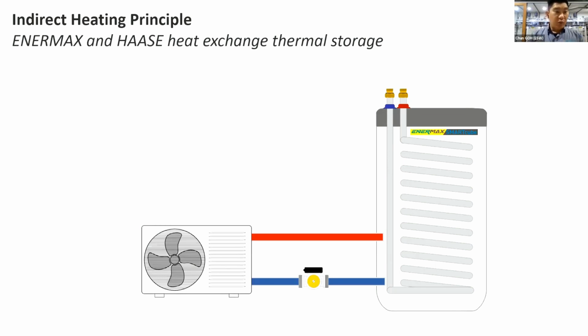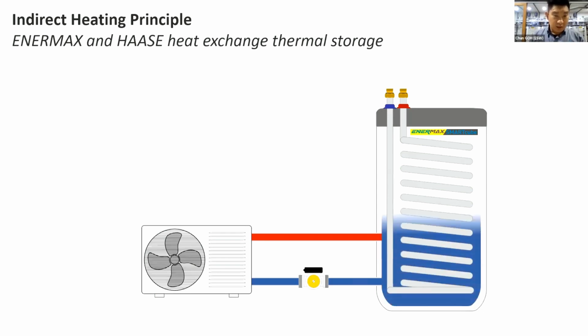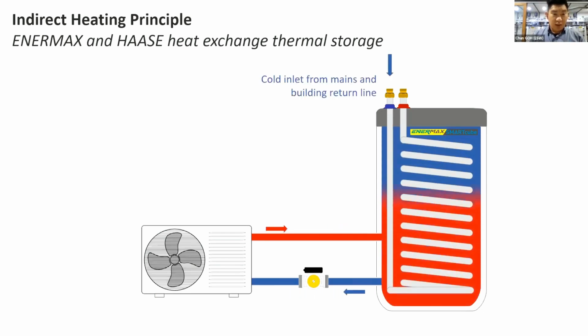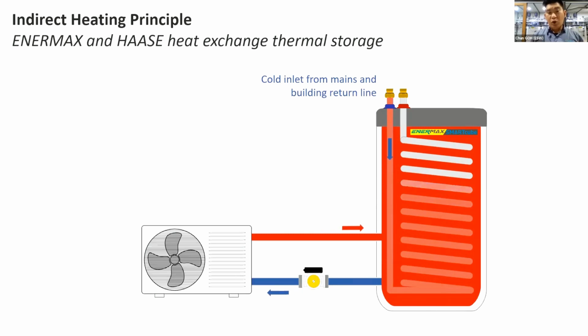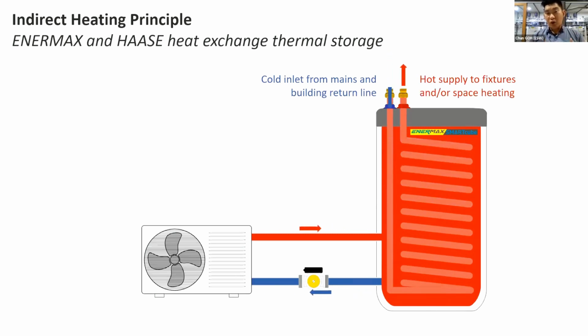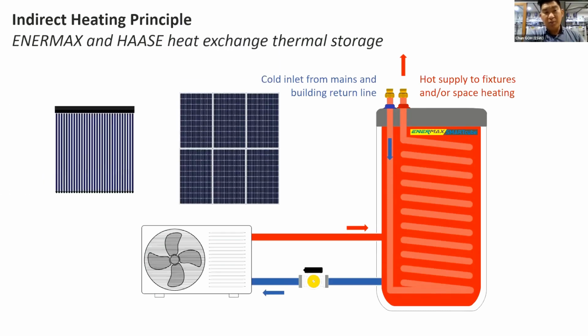If you look at the slide here, heat pump systems have direct systems and indirect systems. We are focusing more on the indirect system, where, if you look at the animation here, the heat pump itself is designed to only heat up the water in the tank, which is not potable water, it's water held in the tank to store the thermal energy. Your potable water runs through the coil—you can see the blue arrow coming down, going into the heat exchanger coil, picking up the heat source, and then coming out, you instantaneously have hot water. So this is how our system is designed.